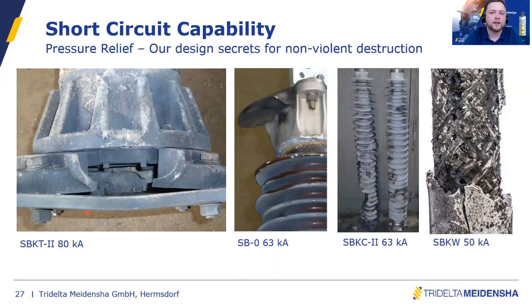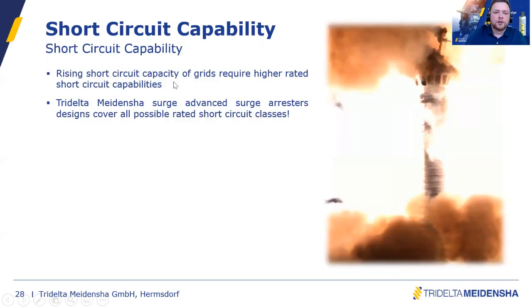So this is our design capability and more or less our secret, how we provide a non-violent destruction in short circuit mode, also for big currents. Short circuit currents have been rising in the past years because the short circuit capability of the grids is rising, and that's why we have to provide surge arrester designs that cover all of the requested rated short circuit classes. For 40 kA, the SBK0 is valid, SBKW is tested up to 50 kA. And then we have the SBKC2, which is tested at 63. Actually, it's tested at 65 kA, so we cover 63.